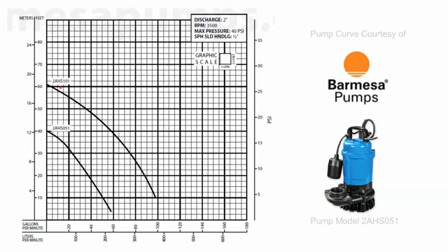Now it's pretty interesting to see how from half horsepower to 1 horsepower you're increasing both the pump's maximum pressure rating, which is indicated here on the left hand side by feet and meters, which is up here at the key. So you can see at half horsepower this pump will produce a shutoff pressure of 40 feet. At the 1 horsepower version of this pump, roughly 61 feet, because it's just a touch over 60.